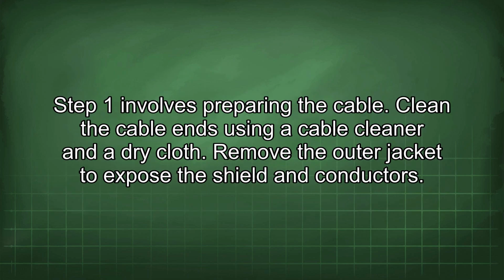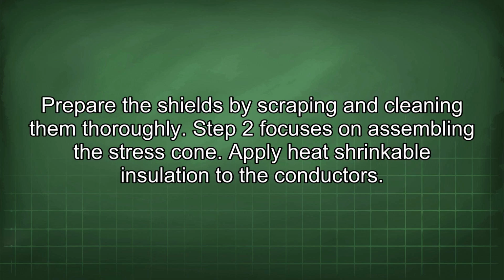Step 1 involves preparing the cable. Clean the cable ends using a cable cleaner and a dry cloth. Remove the outer jacket to expose the shield and conductors. Prepare the shields by scraping and cleaning them thoroughly.